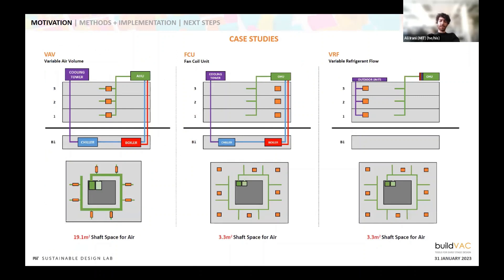We look at another case study: a three-story medium office building — the typical Department of Energy three-story medium office building, which we'll use throughout this presentation. We selected three different HVAC system options for this prototypical building: the VAV system, fan coils, and VRF — variable refrigerant flow. In this slide we're comparing the riser area required — how much area is needed in the core to support these three HVAC systems. We move from a VAV system that requires almost 20 square meters of shaft space just for the air, to something that's more like 3.3 square meters of shaft space for the VRF system.